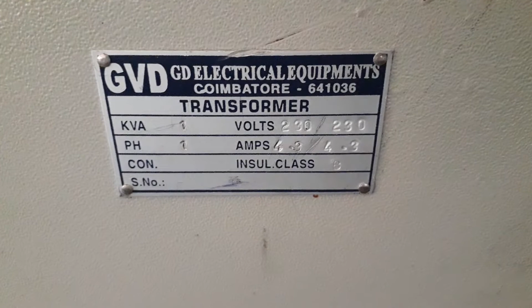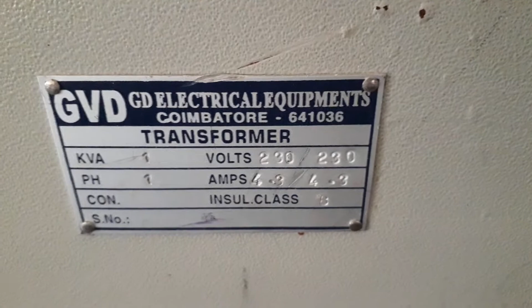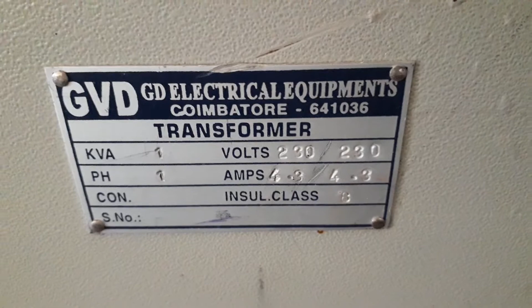Whatever the experiment may be, before doing it you must understand the nameplate details of that particular equipment, whether it is a machine, motor, generator, or transformer. Here it is 4.3 amperes, which means you should not load the transformer beyond this value. If you go beyond 4.3 amperes, what will happen?